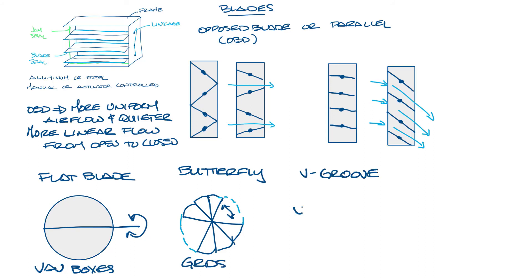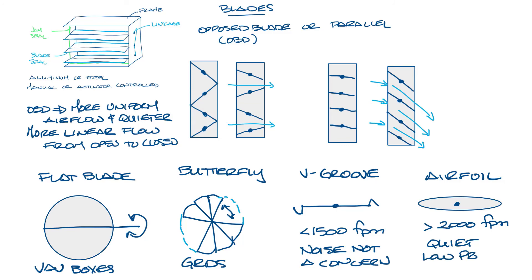There are also V-groove blades that look like this. These are good for velocities less than 1500 feet per minute and where noise is not a factor in the application. If your application is going to see higher velocities or is sound sensitive, you can get dampers with an airfoil blade. Airfoil blades look like this. These blades can have velocities over 2000 feet per minute and are often used when noise is a concern. Airfoil blades have the lowest pressure drop and are typically stronger than other shapes.